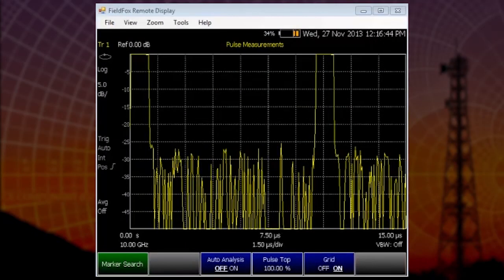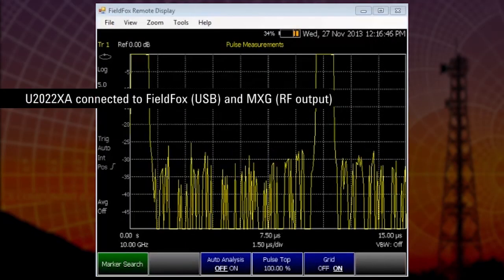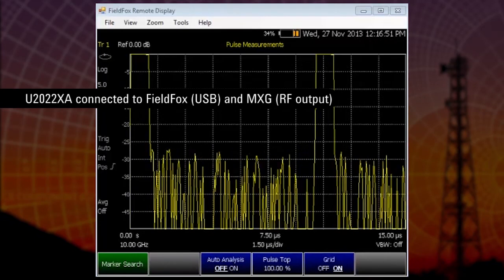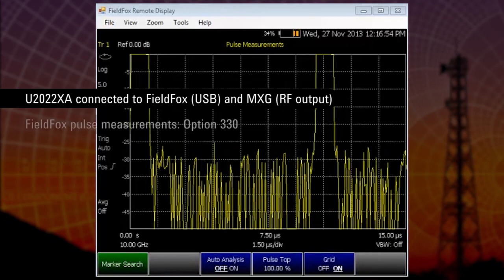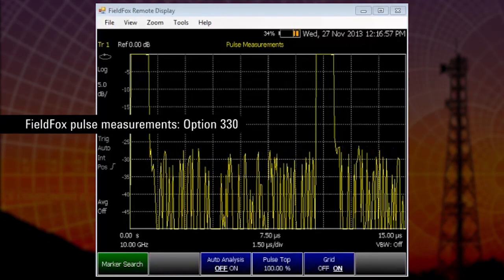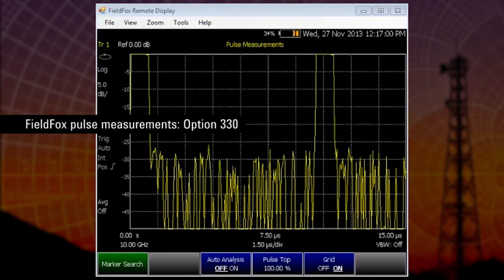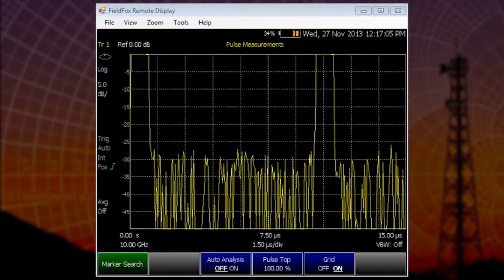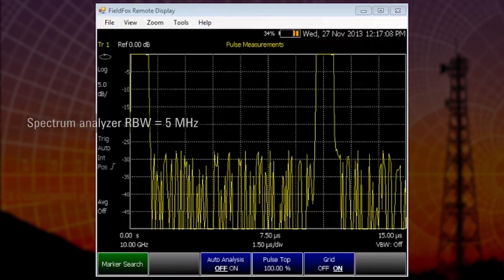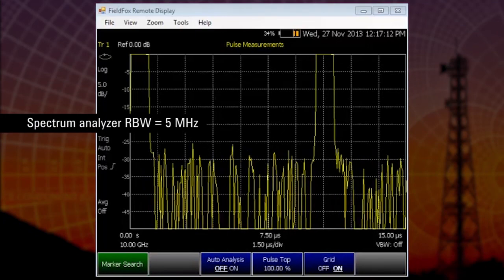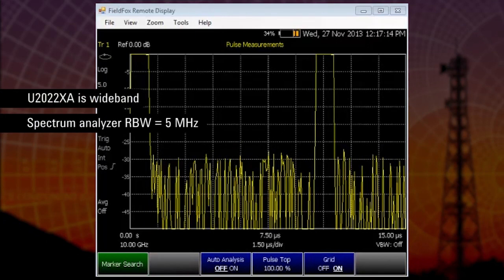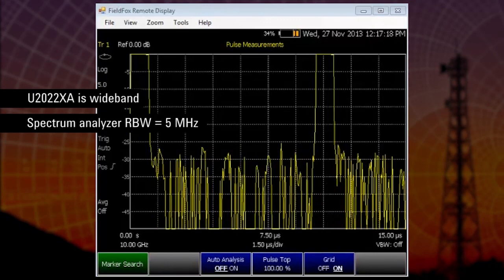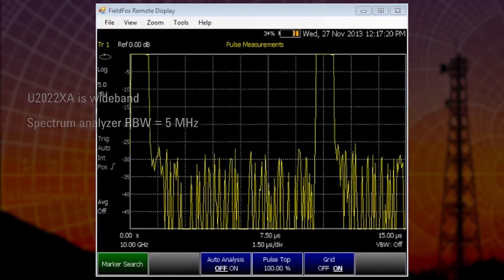I've now connected the U2022XA series peak power sensor to the signal generator and I've switched modes on the FieldFox from spectrum analysis to pulse measurements, which is option 330. You'll immediately notice that the pulses are more crisp than in the spectrum analyzer mode. That's because the spectrum analyzer is limited to a resolution bandwidth of 5 megahertz, while the power sensor is wideband, so it's able to capture more of the pulse spectral characteristics.